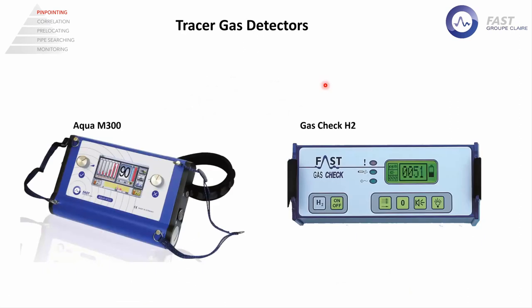Okay, for the tracer gas detectors we have these two products. Again, the AquaM300—you see it's not only a listening device and geophone, it's also a tracer gas detector. This is one of the reasons it's one of our best sellers in the market. You simply connect the tracer gas sensor, and with this you can directly measure the concentration of H2 hydrogen in the field. The standalone unit is the gas check, which can also detect the tracer gas, which usually comes up at the position of the leakage.